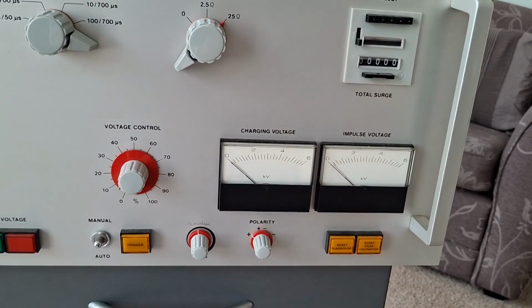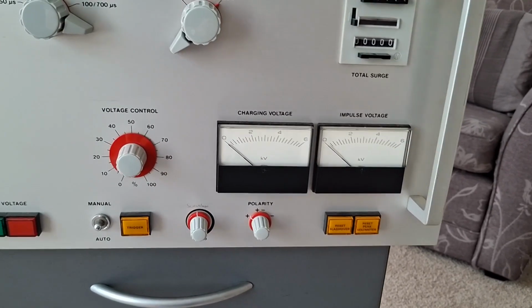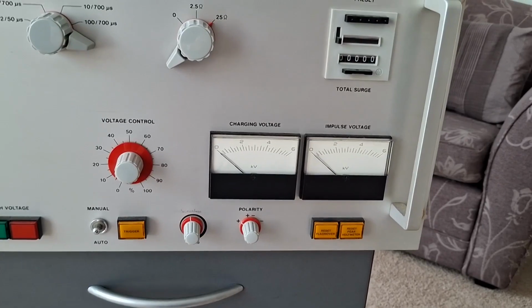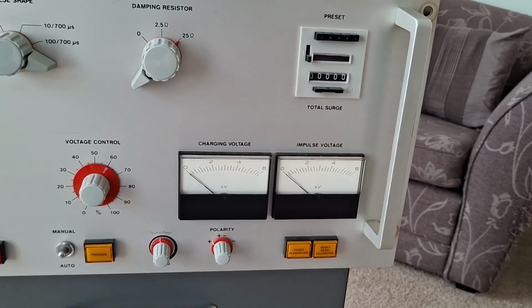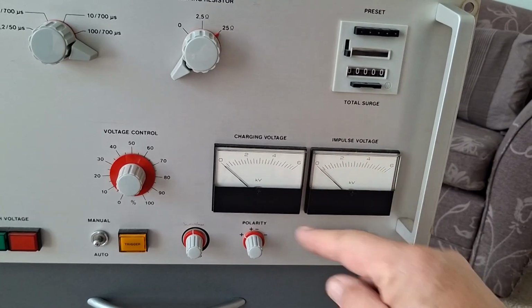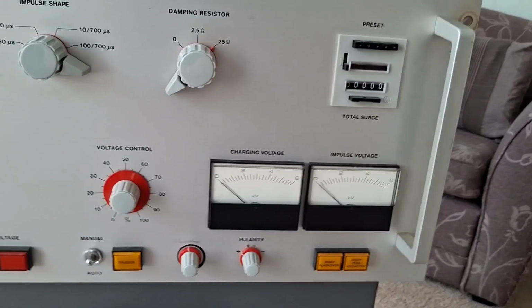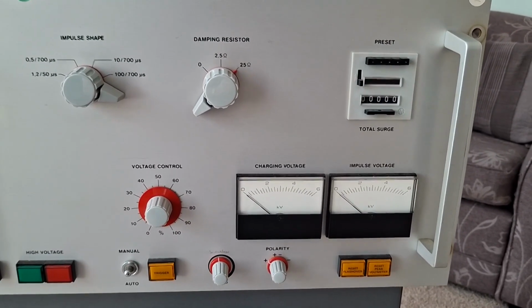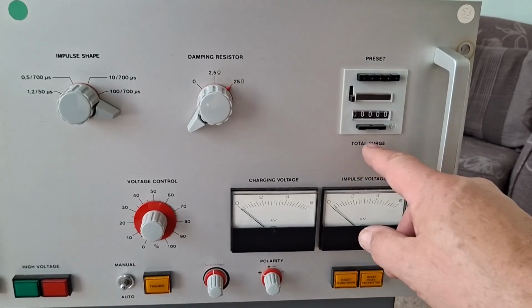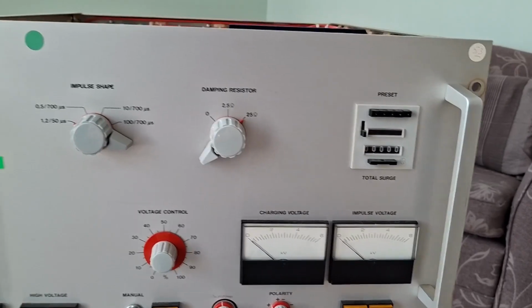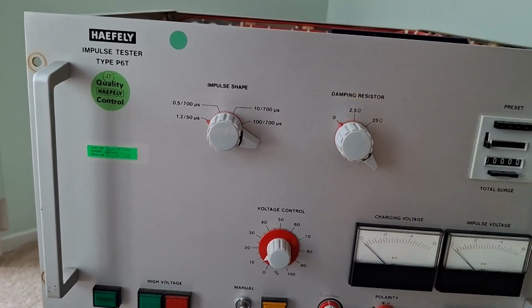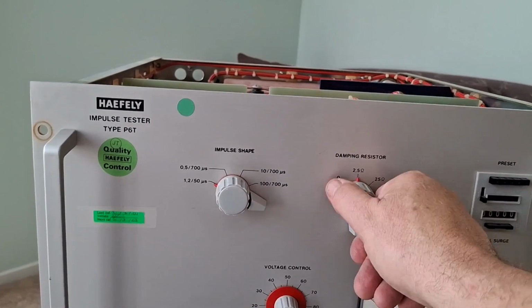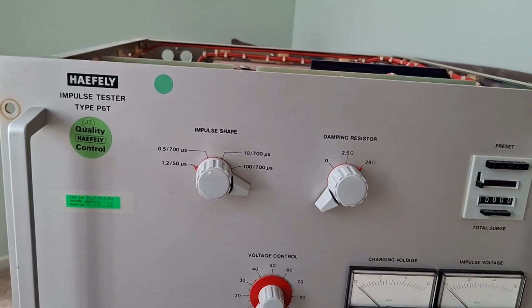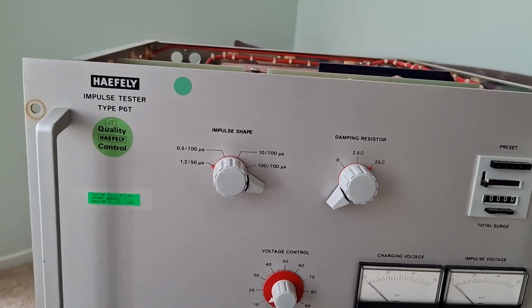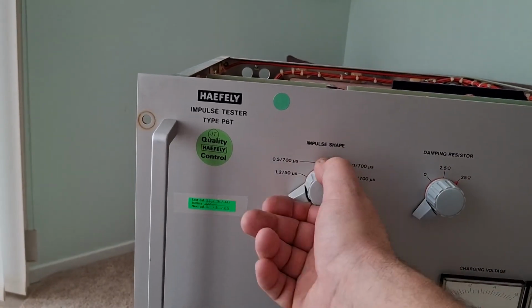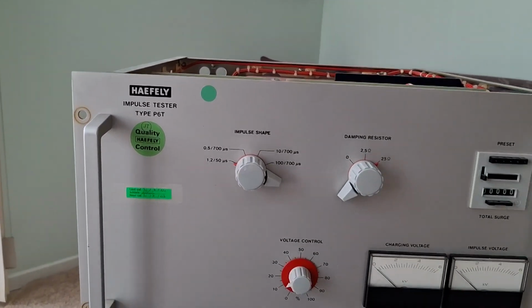There's a reset flash indicator lamp there, so I'd say that if there is a flashover on the device under test, that is the reset for it. And there is a reset peak voltmeter. So the voltmeter here is probably going to record the peak value of the impulse voltage, and that allows you to reset that. There appears to be a surge counter preset. There are damping resistors here, so this will be set up to switch in and out various resistors to change the characteristics of the impulse that you're sending down to the device under test. And there is an impulse shape switch here which switches in and out various capacitors and resistors.